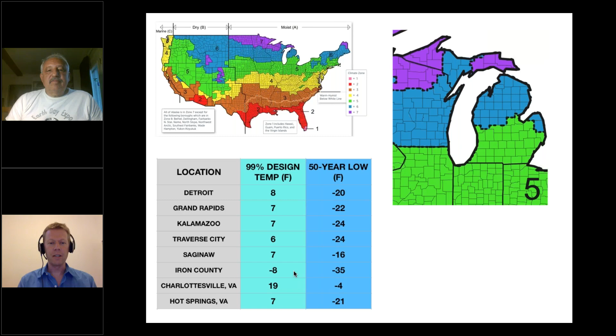And 50-year lows, pulled from the ASHRAE climate tables, I'm seeing around -20, a little colder in a couple of spots. Just for comparison, where I am in Charlottesville, Virginia, our design temperature is 19 and our 50-year low is -4. But we do get pretty cold in some of our mountain spots in Virginia, Hot Springs is 7 degrees and -21. And then for the folks in the UP who are in climate zone 7, you've got some real extremes where heat pumps are more challenging, but not impossible, with -8-degree design temperatures and -35 50-year lows.